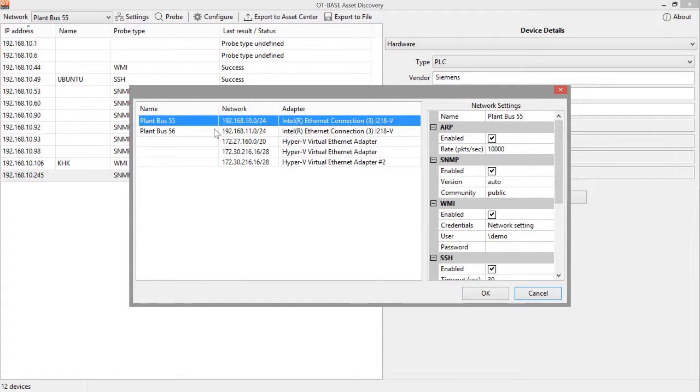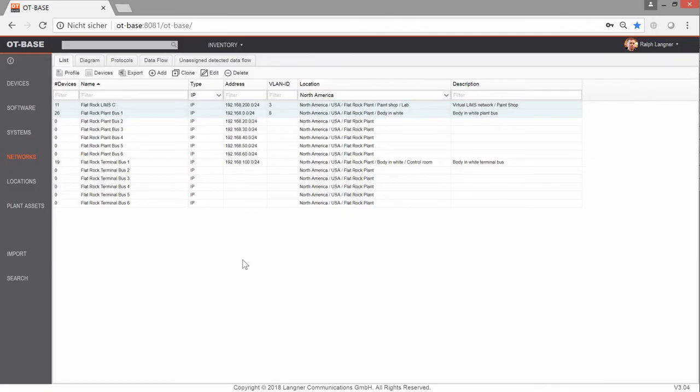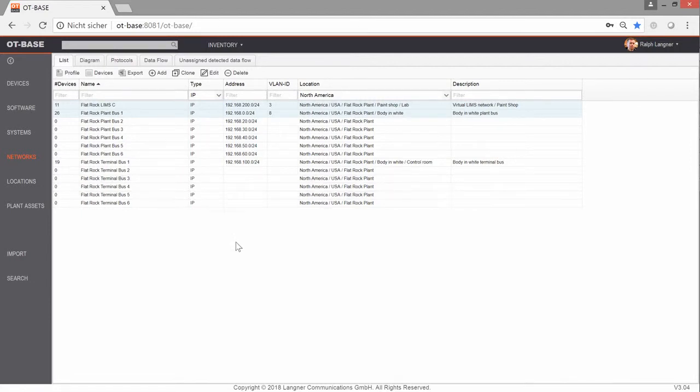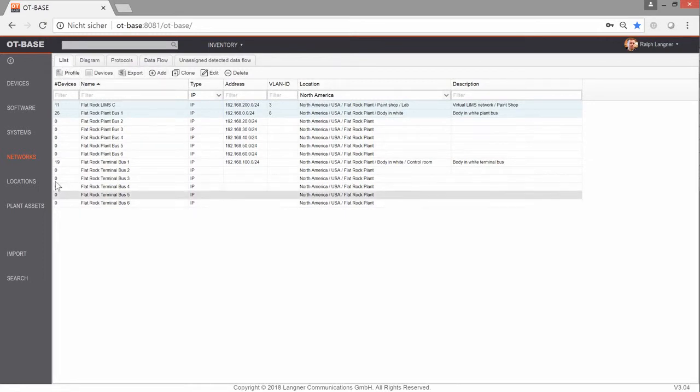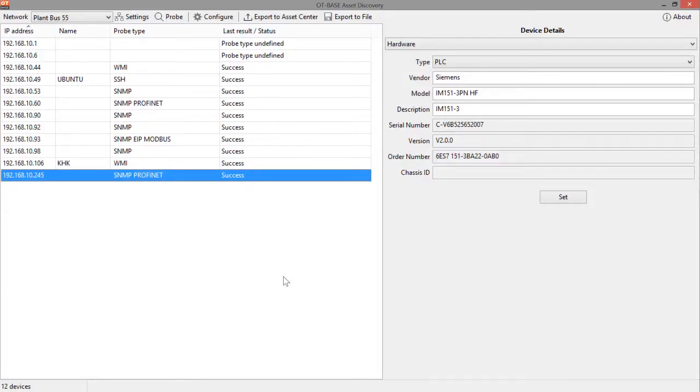So if you have an additional OT-BASE asset discovery node in a different location and you're also using the name PlantBus55 to identify that network then this will result in trouble. Just to give you an idea what happens with that symbolic name it is used in OT-BASE asset center for OT-BASE to manage all those various networks. It is perfectly fine if you're using identical IP addresses for different networks but you cannot use identical names. So in the inventory in the networks list you will see all your networks listed by symbolic name. And with that we're almost done.